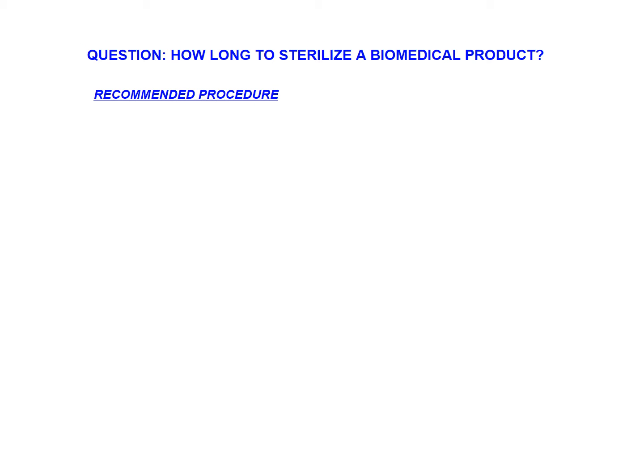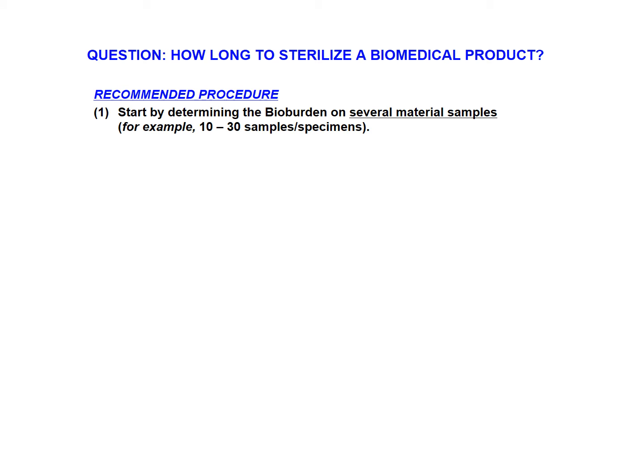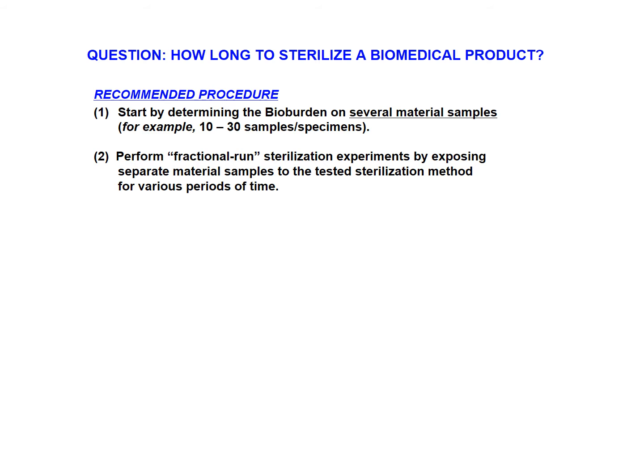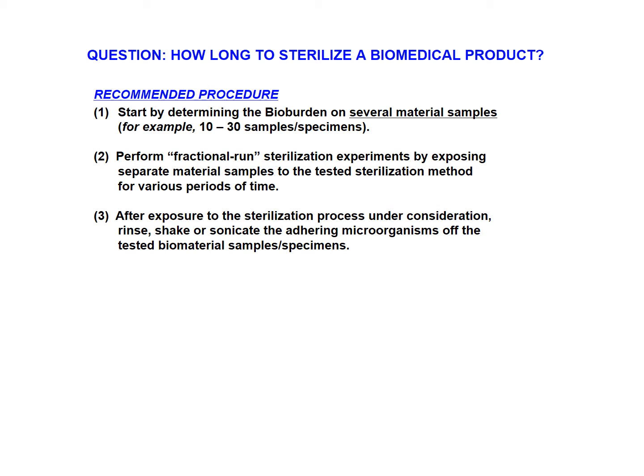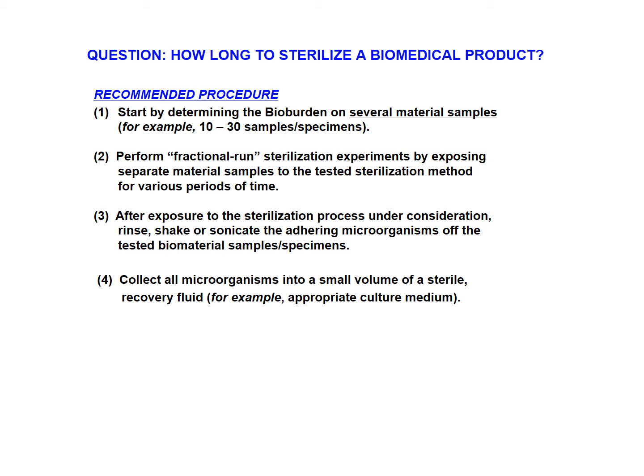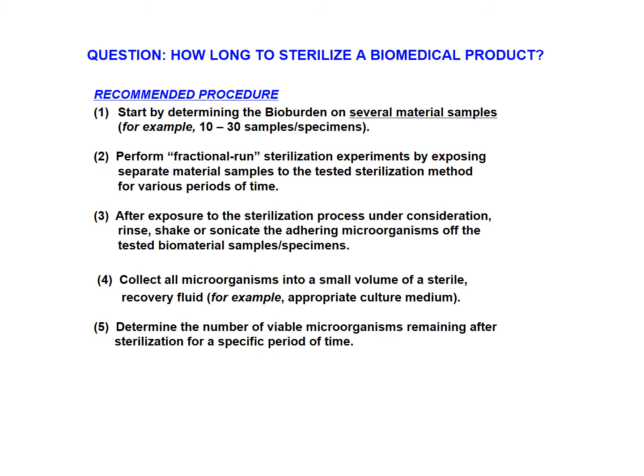For this purpose, the recommended procedure is as follows. Start by determining the bioburden on several material samples, for example, 10 to 30 sample specimens. Perform fractional run sterilization experiments. These experiments expose a smaller number of the specimens separately to the tested sterilization methods for various periods of time. After exposure to the specific sterilization process, rinse, shake, or sonicate the adhering microorganisms off some of the tested biomaterial samples. Collect all these microorganisms into a small volume of a sterile recovery fluid, for example, an appropriate culture medium, and determine the number of viable microorganisms remaining after sterilization for a specific period of time.